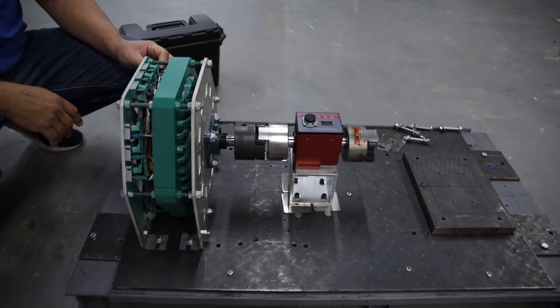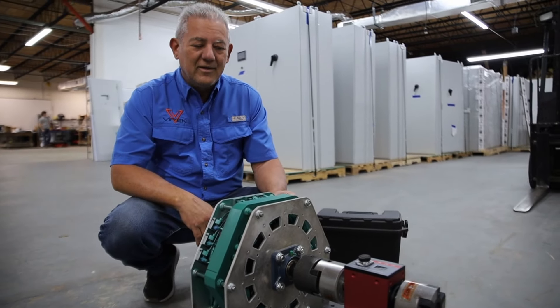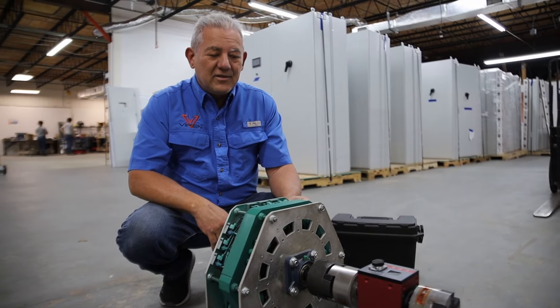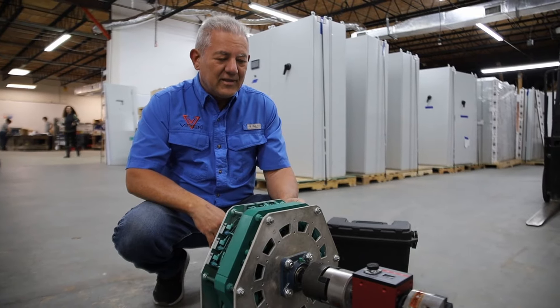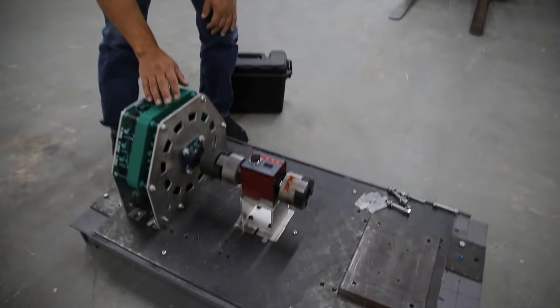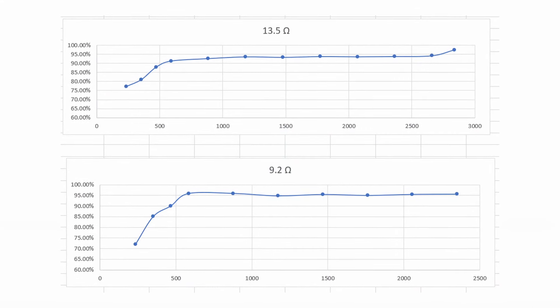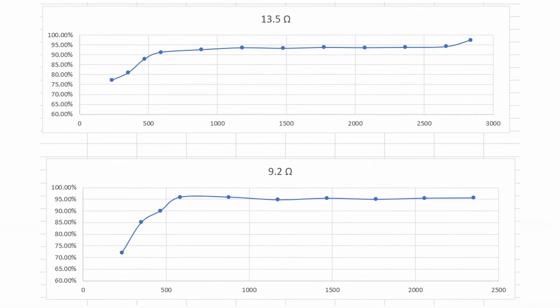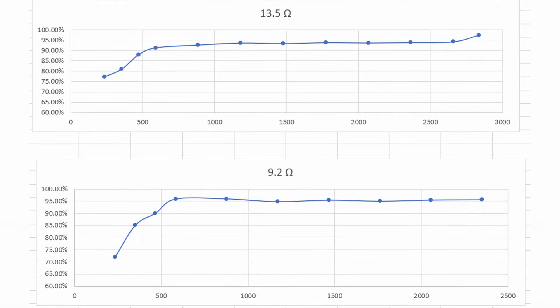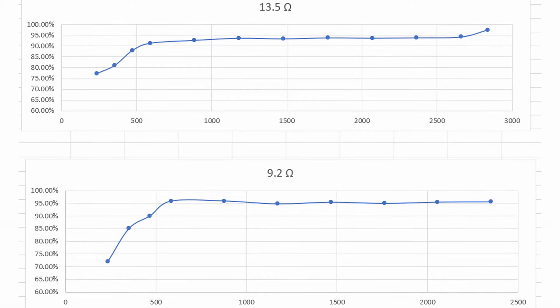With this unit here we've shown efficiencies that are much greater than anything we've seen before, in character as well as in actual wattage and percentage of efficiency. The key thing we've found is that we've been able to completely modify the curve of performance of actual percentage of efficiency. So instead of having a natural inclining curve that you see in almost any generator, we've taken it up and across and broadened the overall efficiency range — so it really works well with wind applications.